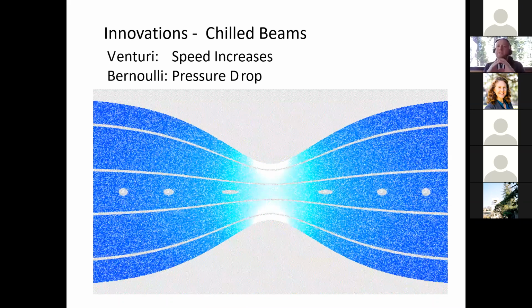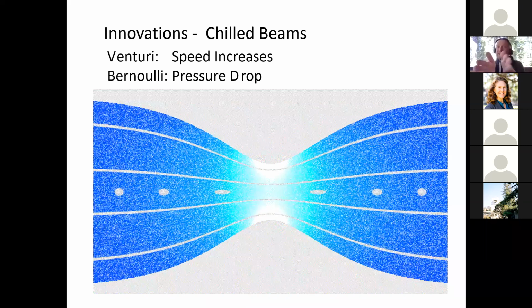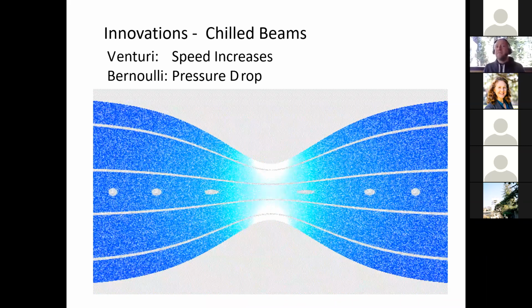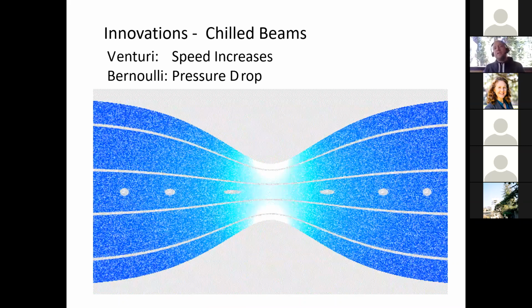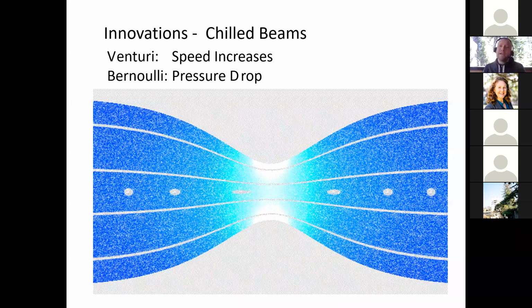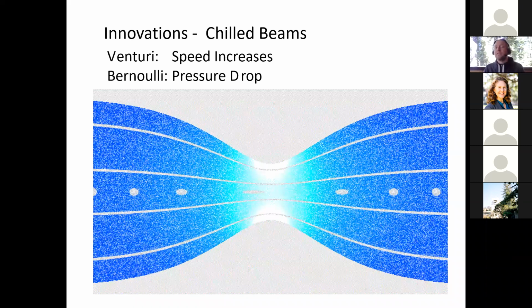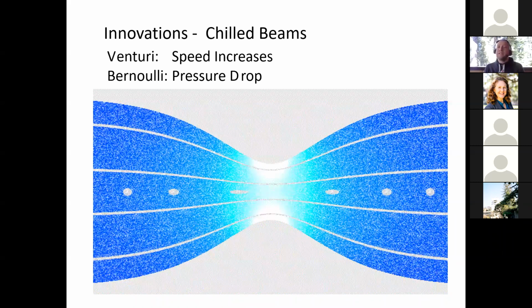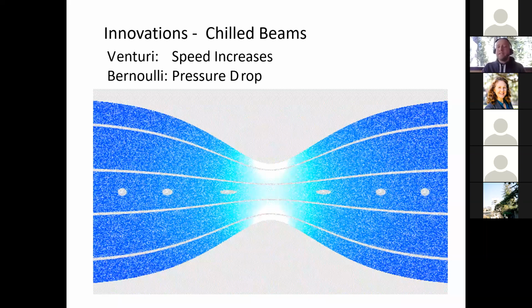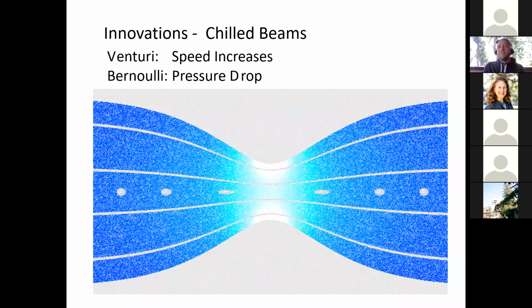So if you have a smaller orifice, a smaller restricted space, and you're trying to push the same amount of air through it, or fluid, it has to increase in speed. And then what we know from our Bernoulli equations from fluids is that once you have a higher velocity flow, you're actually going to get a lower pressure. So the pressure within that space is actually going to drop as the velocity increases. And so we can actually take advantage of those two factors when we look at chilled beams.